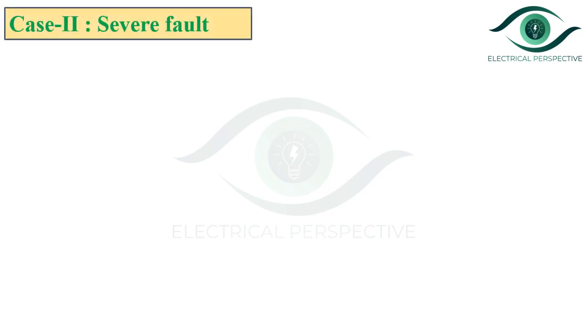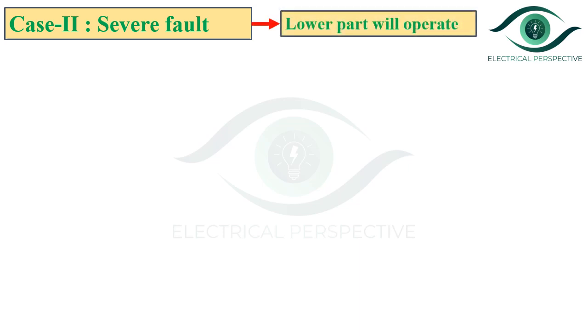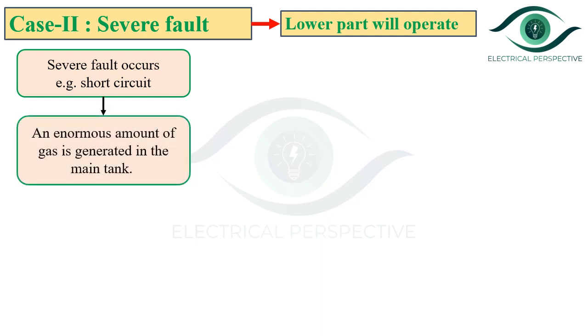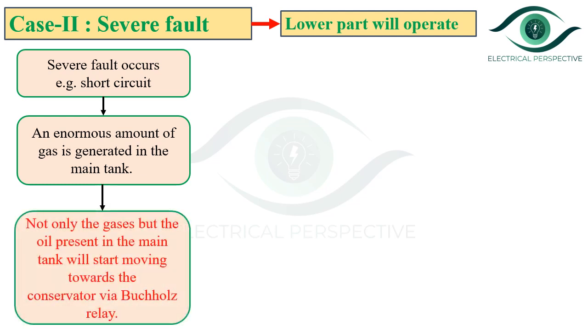Now let us consider case 2, that is the severe fault, so the lower part will operate. When a severe fault occurs in the transformer — for example, a short circuit — an enormous amount of gas is generated in the main tank. Not only the gases, but also the oil present in the main tank will start moving towards the conservator via Buchholz relay. Note: in case of less severe fault, only gases travel from main tank to conservator, but in case of severe fault, the oil also moves towards the conservator via Buchholz relay.